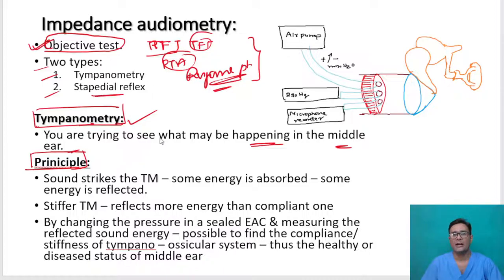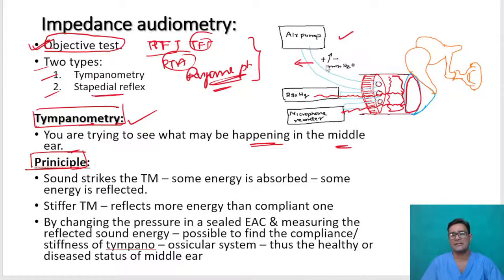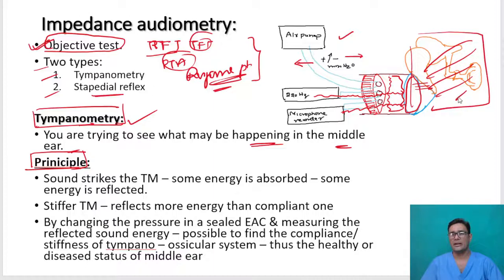What is the principle of this test? When you send sound energy through this probe and it strikes the tympanic membrane — if the tympanic membrane is stiff, it reflects more sound energy. If it is lax or very compliant, it reflects less sound energy. That reflected sound energy is picked up by the microphone. By changing the pressure in the external auditory canal with the help of an air pump, we can go from minus 200 or minus 400 mm of water to plus 400 mm of water.